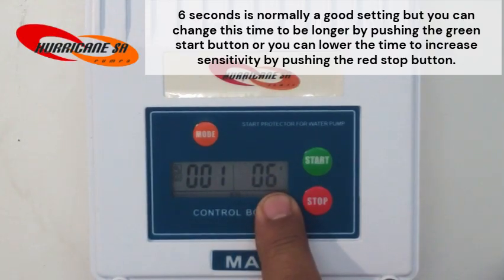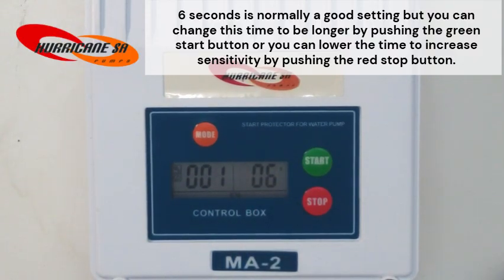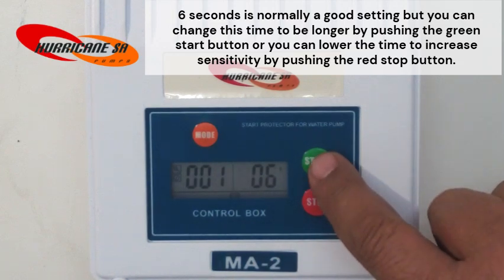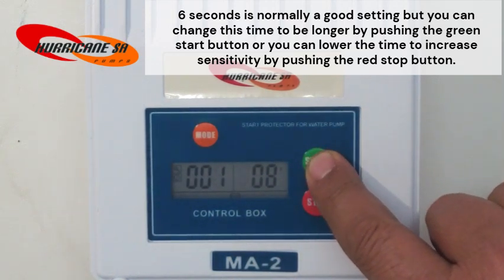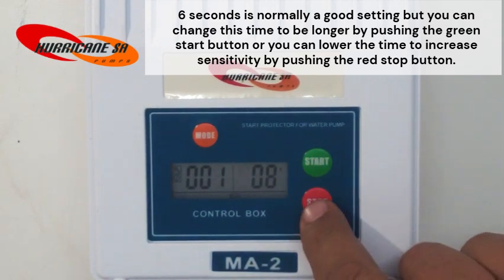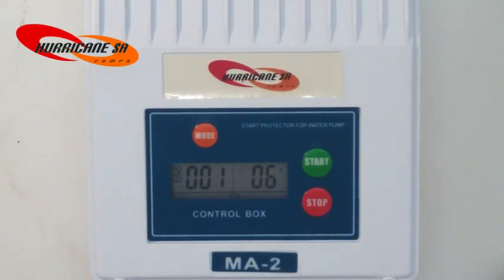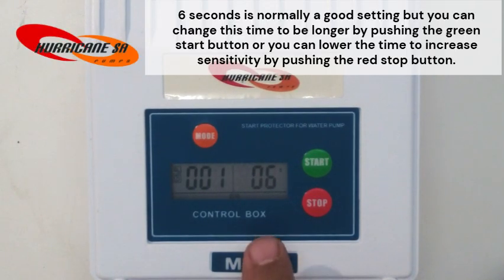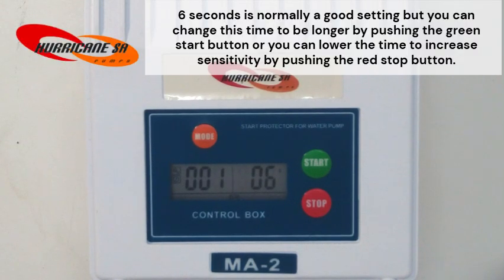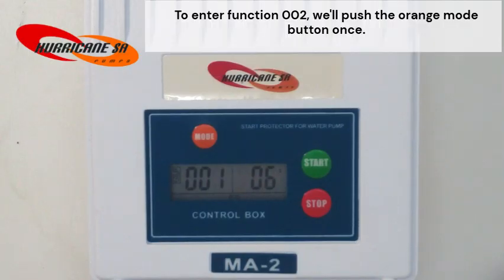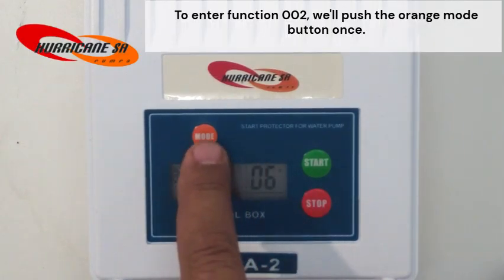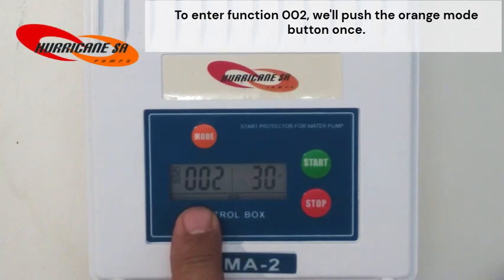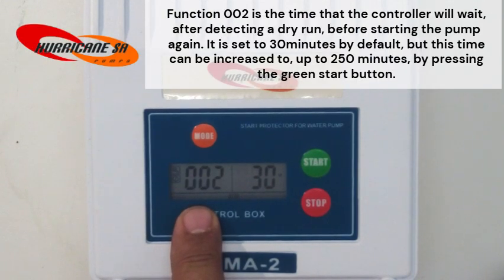6 seconds is normally a good setting, but you can change this time to be longer by pushing the green start button. Or you can lower the time to increase sensitivity by pushing the red stop button. If there are no special conditions with your pump setup, you can leave this dry run time set to 6 seconds. To enter function 002, we'll push the orange mode button once. Function 002 is the time that the controller will wait after detecting a dry run before starting the pump again.